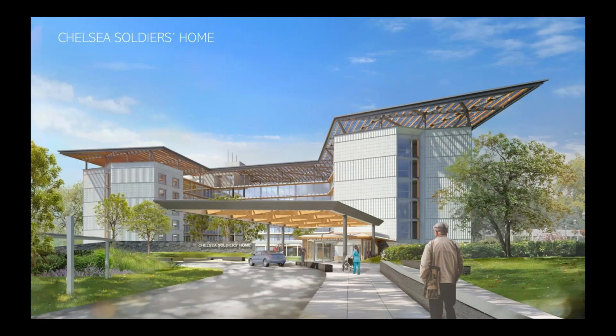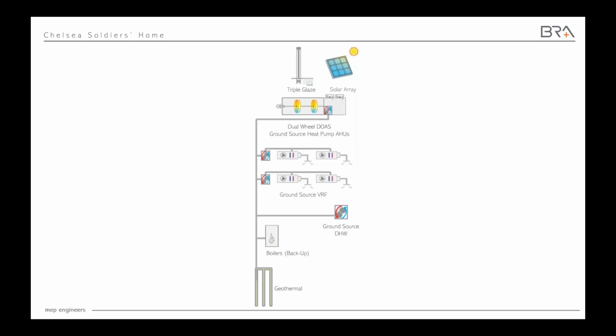It's a 250,000 square foot assisted living facility, has a full service kitchen. It's essentially if you took a hospital and you chopped off the patient bed tower, right, and just put that on its own site. It has to meet all the ASHRAE 170 air change requirements like a normal inpatient unit for a hospital. It has a reduced window to wall ratio, it has triple glazing, it has a 0.5 megawatt solar array canopy above the building. But the real trick of this is how are we getting off of fossil fuel?